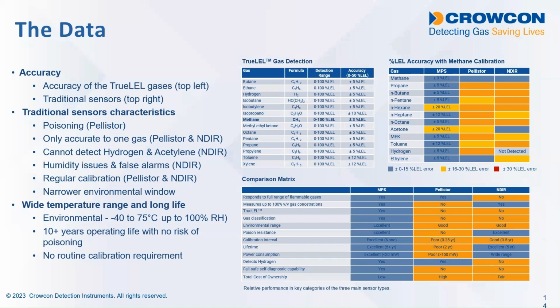And as I said, the Pellistor is only accurate for the gas that it's calibrated for, but you can calibrate it for hydrogen. It will be accurate for hydrogen if that's your primary risk in your environment. The Pellistor also has a short life, so if it sees a high concentration of gas, it's likely to burn out. And as I say, it does need regular calibration. Pellistors can also give false readings if there are big swings in pressure, humidity or temperature in the environment. The Pellistors generally work over quite a wide temperature range, up to about 50 degrees Celsius.